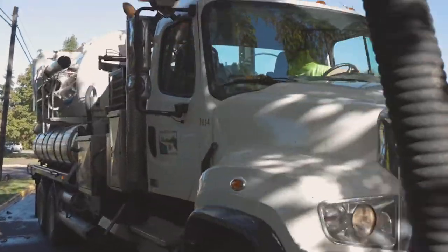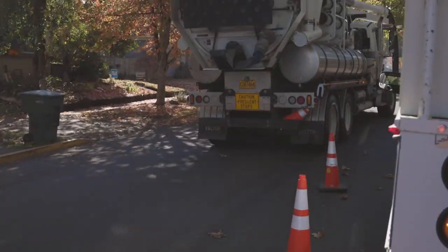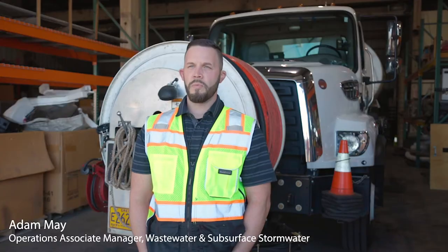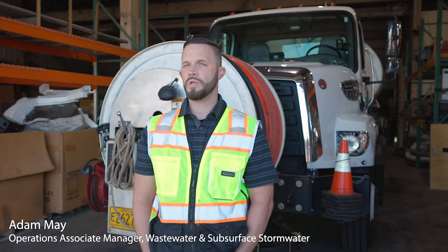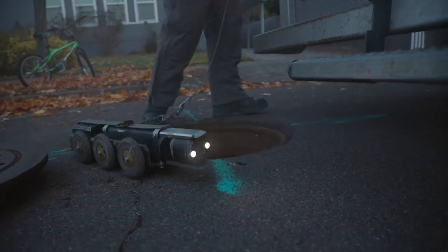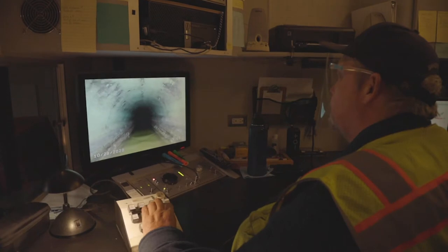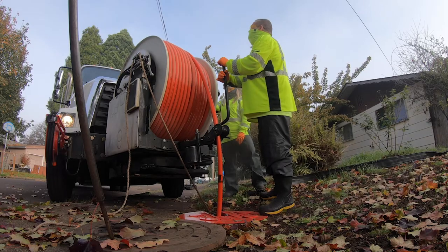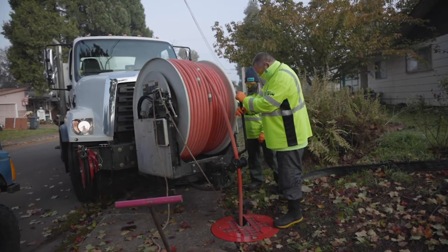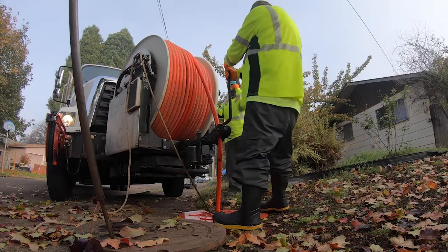In addition to repairs and rehabilitation projects like this one, the CMOM program guides our proactive maintenance efforts to prevent leaks before they even happen. Some of our preventative maintenance — and these are usually daily — would be closed circuit TVing, which is sewer inspection through camera. We run a camera system up the sewer line and we visually inspect the insides of the sewers. We also do high velocity cleaning, which is a high-pressured water truck that will clean the insides of the sewers, and we can use it for breaking through blockages, grease, and roots.